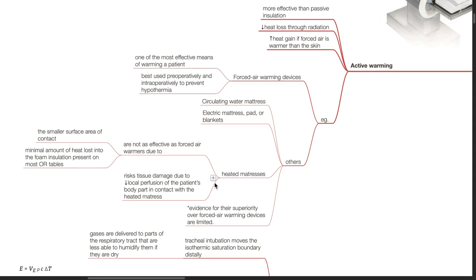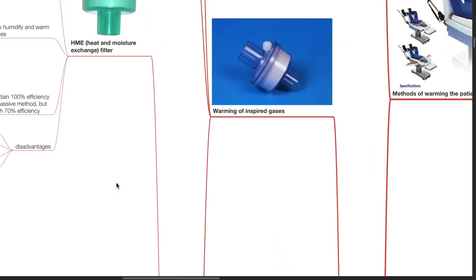Regarding heated mattresses, these are not as effective as forced air warmers due to the smaller surface area of contact and the minimal amount of heat loss into the foam insulation present on most OT tables. Heated mattresses risk tissue damage due to reduced local perfusion of the patient's body part in contact with the heated mattress.